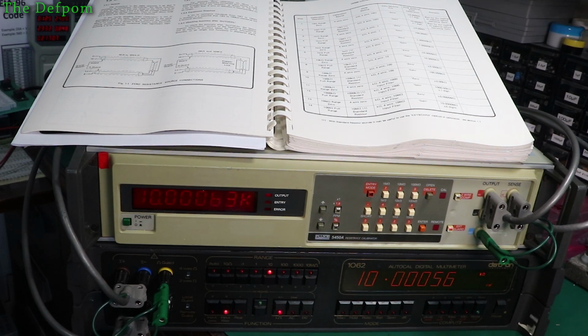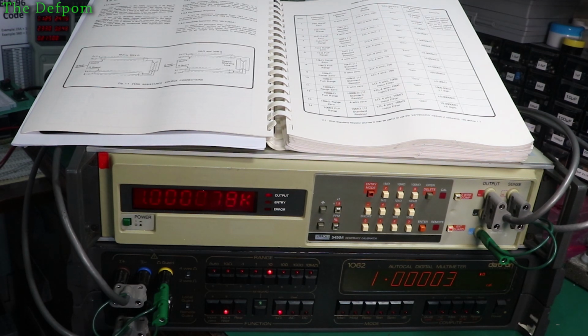See how we get. So reading a little bit low there. So there's definitely some kind of linearity issue there. It's not a big issue, but it's very slight. If I do 1k, well, that's pretty much it, isn't it? You know, 1k is a bit hard to measure. 100 ohms. See what it thinks of that. Yes, that's very slightly out there, but it could have been due to zeroing as well. Zeroing wasn't perfect in this one. It was going negative, you see.